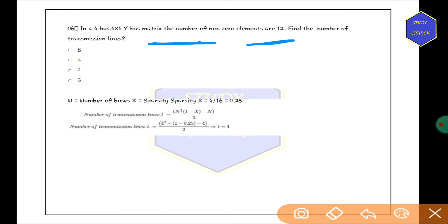Next, in a 4 into 4 Y bus matrix, the number of non-zero elements are 12. Find the number of transmission lines. So we know by the formula, n squared (1 minus x) minus n, by 2. This is the formula of number of transmission lines. So it is 4 squared, then we have 1 minus 0.25 as the sparsity as we found out earlier as well. Then n is 4, then we have 2. So on solving this, t comes out to be 4. So 4 is the answer.